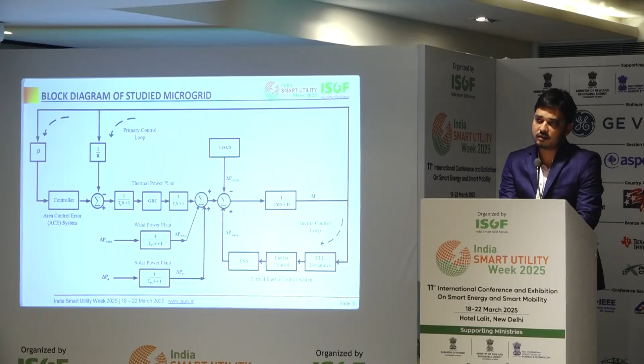Next, second is the optimization of the fault passage indicator. All of you know that the fault passage indicator indicates where the fault is in the system. But the major thing is whether it is a radial network or an interconnected network. For renewable-energy-based systems, what is the major disadvantage? If renewable energy is connected to the system, there is a reversal, meaning bidirectional flow of energy. For bidirectional flow of energy, the normal FPI does not indicate the faults. We cannot properly measure where the fault is in the network.